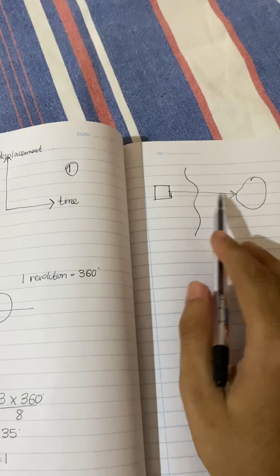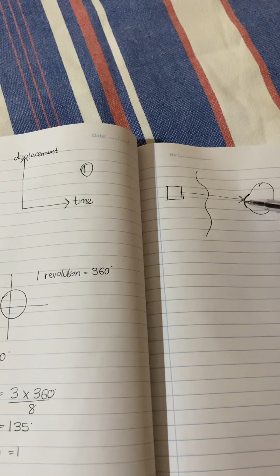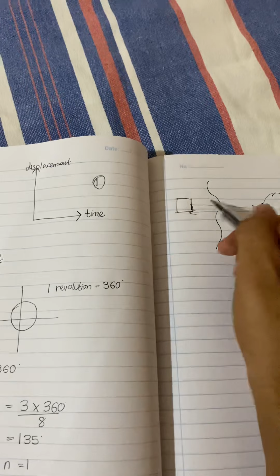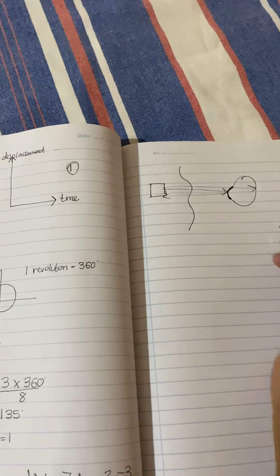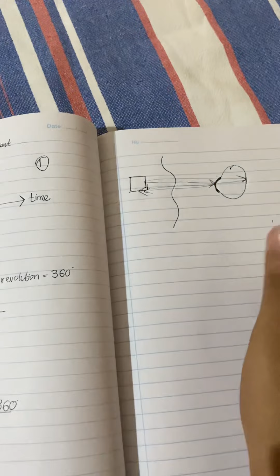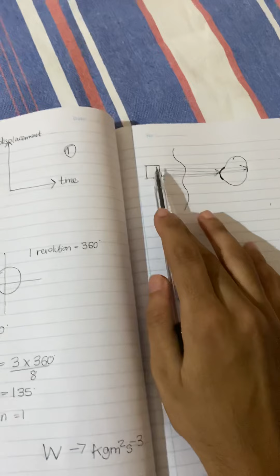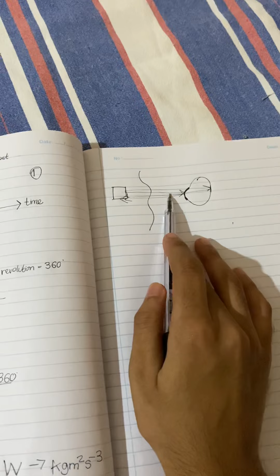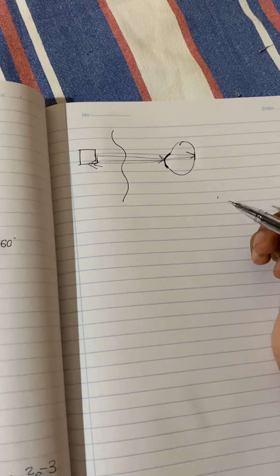From the transducer, you're going to send waves. Whenever there's an obstacle, like here, it will reflect it back. And then again, it will emit the second signal. And here, there's an obstacle, so it will send the ray back. Because of that, ultrasound is emitted in pulses, because one pulse must return before the next pulse is sent, so that the time interval between the transmitted pulse and the received pulse can be more accurately determined.